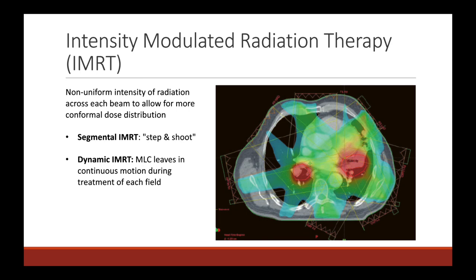One way of doing IMRT is segmental IMRT, where the beam positions itself at the correct angle, the MLC leaves come into place, and then the radiation is given all at once in what is called a step-and-shoot approach. There is also dynamic intensity modulated radiation, where the MLC leaves can actually continuously move while the radiation is being delivered. IMRT helps us create much more conformal dose distributions — the red area of the color wash, which represents our therapeutic radiation dose, is really conformal to the drawn target organ we want to treat.